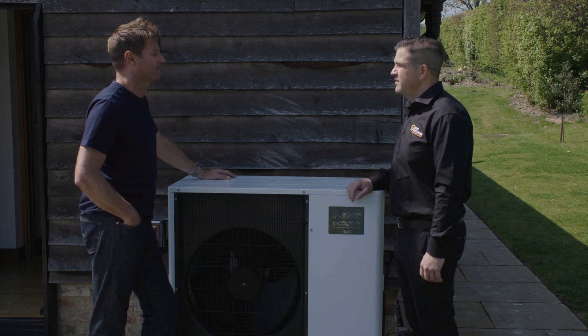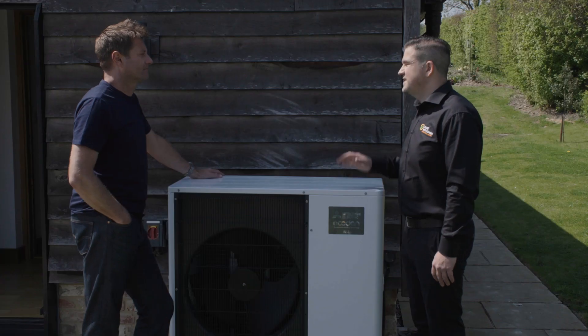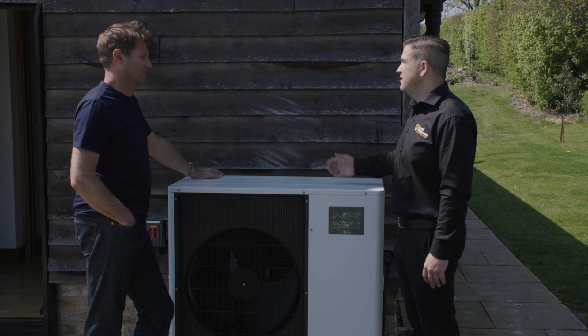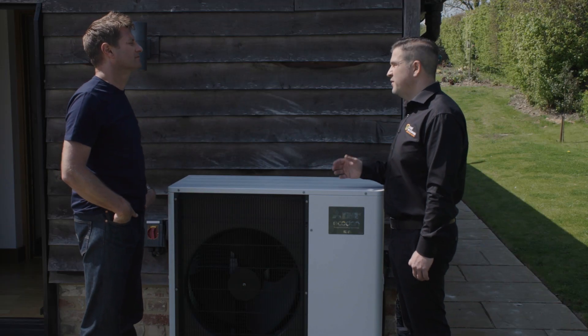Jason Woods from Dore Woodman Renewable Heating explains the installation process. To work out what size EcoDan unit is needed, they first look at an EPC — an energy performance certificate — which gives information on cavity wall insulation, floor insulation, loft insulation, and so on. Once the building fabric is established, they carry out a room-by-room heat loss calculation, measuring floor to ceiling, wall to wall, windows, and any radiators. This allows them to precisely size the heat pump to provide 100% of the heating and hot water. For any MCS-accredited business, this should be done before every single installation.